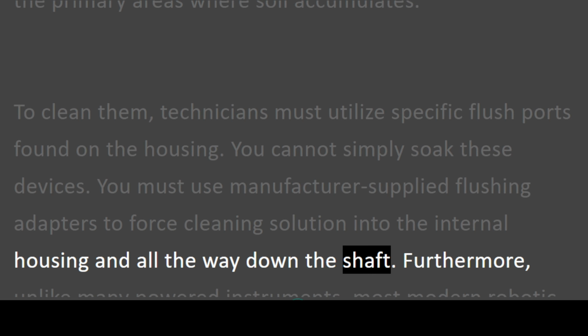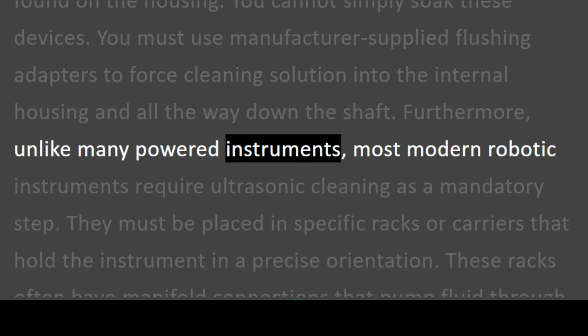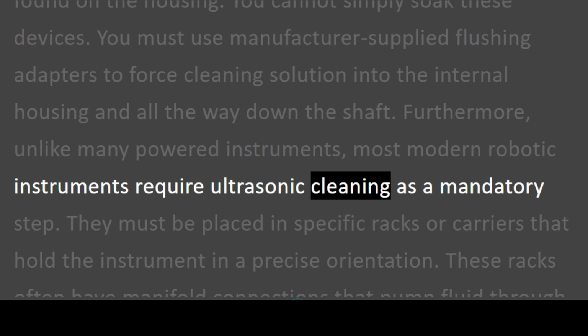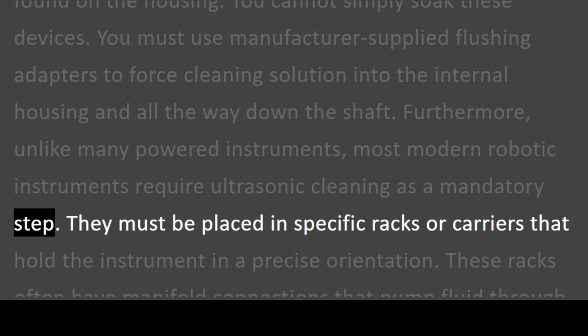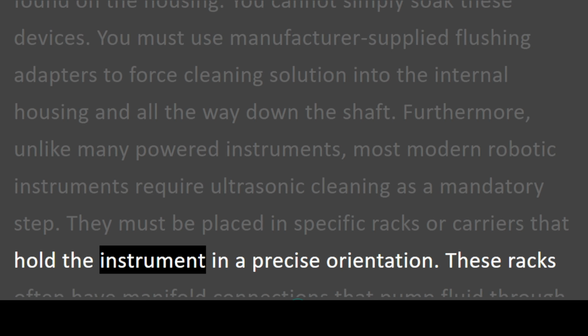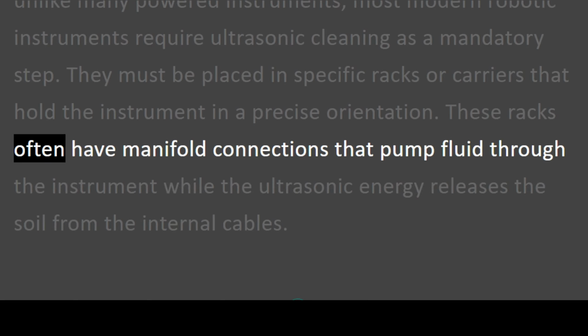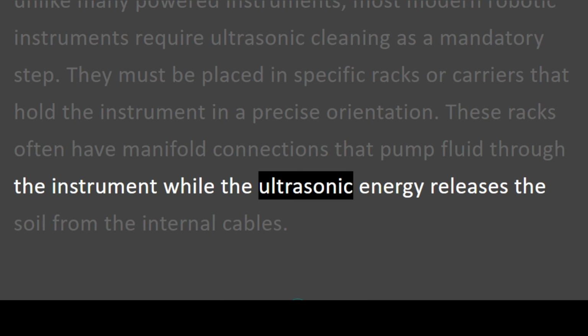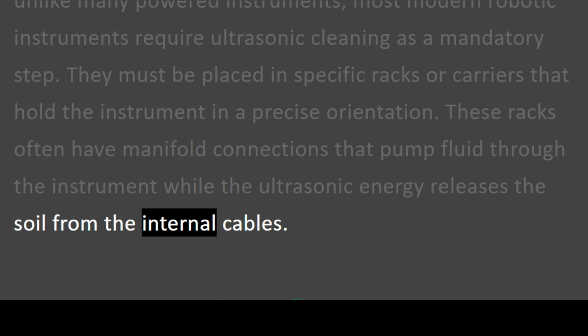Furthermore, unlike many powered instruments, most modern robotic instruments require ultrasonic cleaning as a mandatory step. They must be placed in specific racks or carriers that hold the instrument in a precise orientation. These racks often have manifold connections that pump fluid through the instrument while the ultrasonic energy releases the soil from the internal cables.